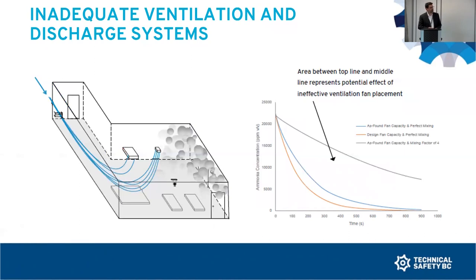There was an area of smoke accumulation along this wall, where you could see that it's outside of the established airflow. And what's important about this is that this accumulated smoke was right next to the vestibule door. And that would be the normal entry area in response to an ammonia leak.